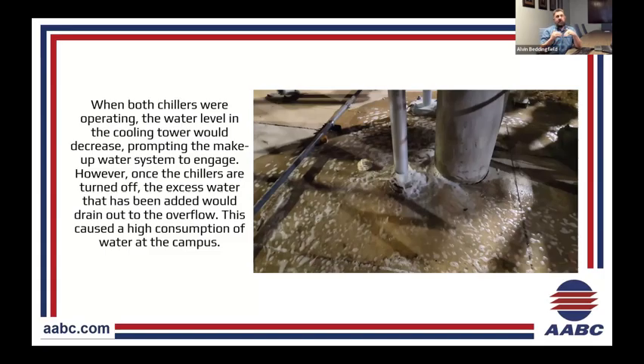But just having that water nonstop, we reached back out to the mechanical supplier and said, okay, we're just teeter-tottering on this. We can't figure this out. We can't set the basin properly. It's either we're slightly pulling some air in and eventually we lose a chiller randomly, it just gets a little pocket of air into the pump and cavitates and loses flow, or we're just dumping out water and wasting chemicals and wasting the district's water connection, or water service to the tower. So it was around and around, back and forth.